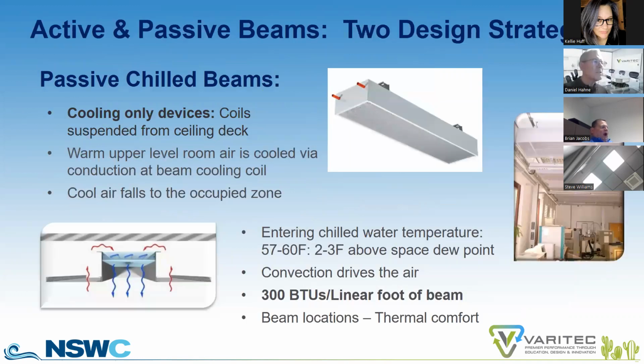So let's look at passive chill beams. These are cooling only devices, and the reason being, well, if you warm air in the upper levels of the room, that warm air is going to stay in the upper levels of the room, and it'll be a long time before that energy finds itself down into the occupied zone. So what you do want to do, though, is create a thermally stratified environment where you maintain a room thermostat at 75 degrees, and the upper levels of the room will be warmer at approximately 78 to 80 to 82 degrees, depending on room load, elevation, height of that room, etc.